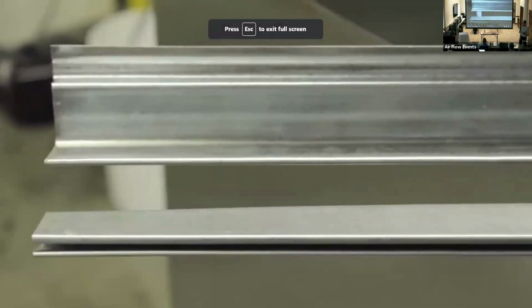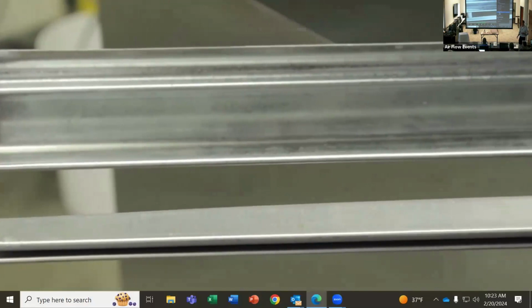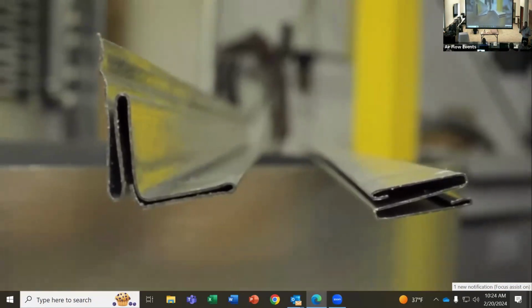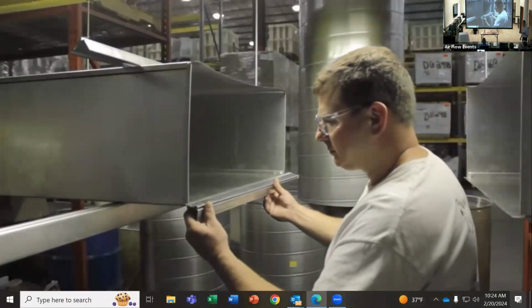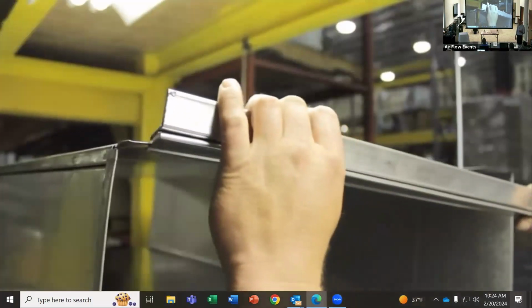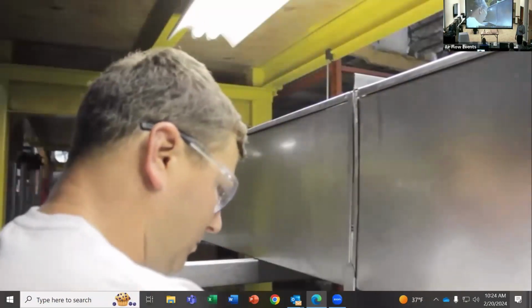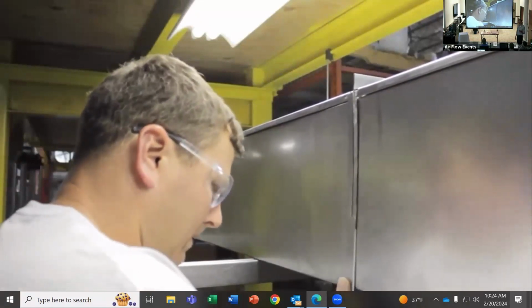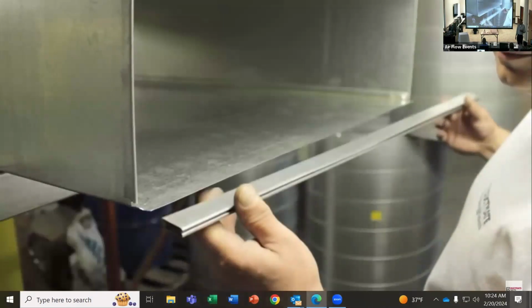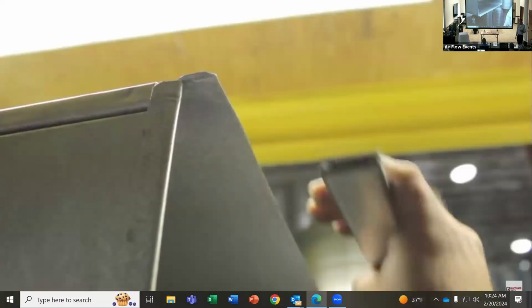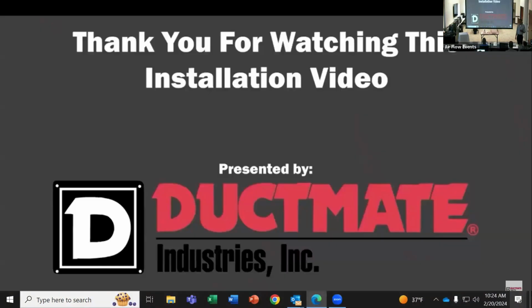Play the whole thing. Here at Ductmate Industries, we manufacture standing S and hem slip drive, which is used for residential or light commercial duct, depending on the duct size. The standing S is cut 1/2 inch shorter than the duct size and installed on the raw edge of top and bottom of the duct. Bring the duct together on one side and drive the drive cleat on and hammer the tab over on each end of the drive. Repeat process on opposite side. The hemmed S slip is also cut 1/2 inch shorter than the duct size and is installed on the raw edge of the top and bottom of the duct. Review product spec sheet for available alloys, gauges, and cut the length of slips and drives. Thank you for watching this video from Ductmate Industries.